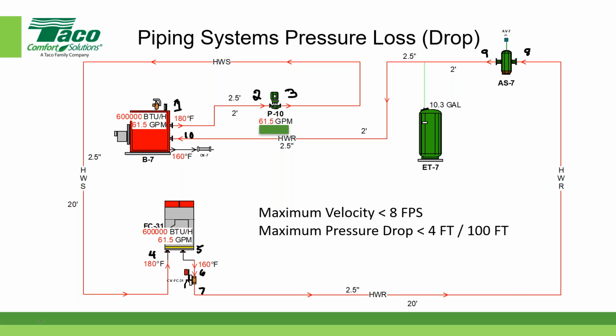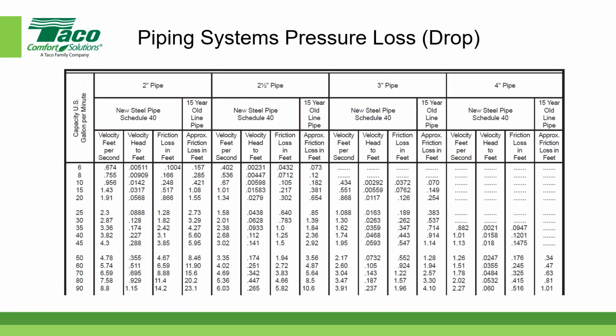Yep. Okay, if you'll notice, our little system here has 61.5 gallons per minute. And I'm going to come back to the slide in a second. So my first thought would be, well, can I do that with 2-inch pipe? Well, you can see I don't have a value here. Let me try erasing that. One more time. Try erasing it one more time, Rich. Okay. So I don't have a value for 61.5, but I do have one that's fairly close. I've got 60 gallons per minute.